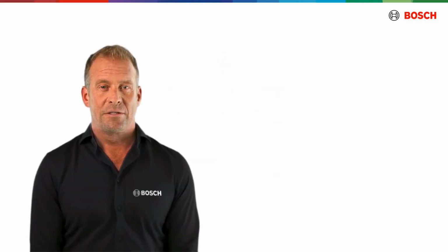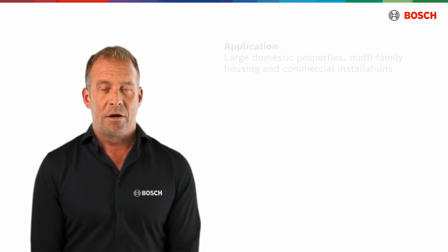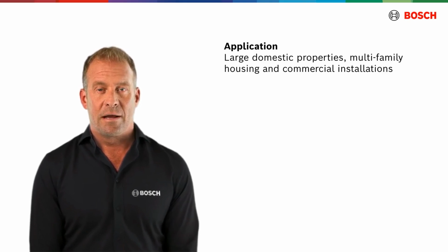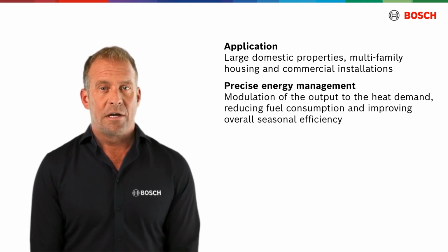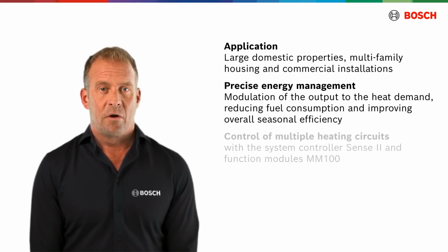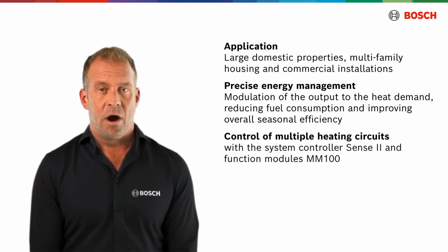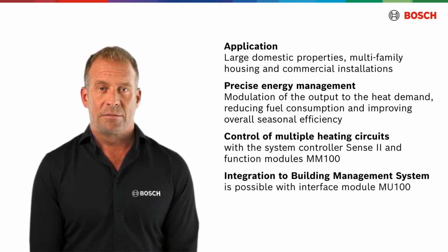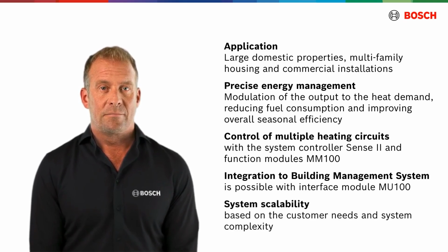Here are the key benefits of using the EMS-based control systems. They can be used in large domestic properties, multifamily housing, and commercial installations. They provide precise energy management, modulating the output of the boiler to the heat demand, reducing fuel consumption, and improving overall seasonal efficiency. System controller Sense2 can control up to 4 mixed or unmixed heating circuits and up to 2 cylinder circuits. A straightforward integration into the building management system is possible via interface module MU100. Heating systems could be expanded based on the customer needs and system complexity. Other technologies like solar thermal can be easily included into the system.